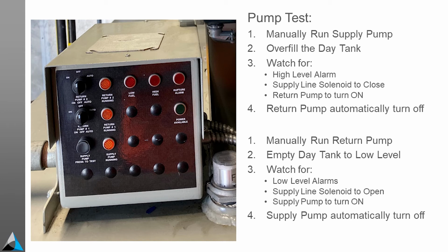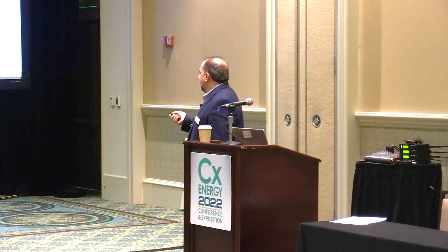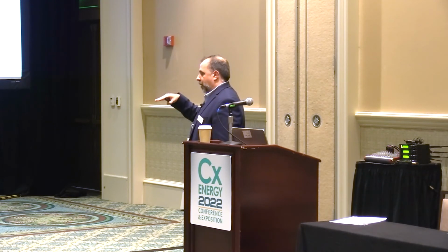So I'm ready to test the fuel system. This is generally how I'm doing it when we get to functional testing of the fuel system. I'm going to test the supply pumps. I'm going to try to overfill the day tank. This is where the videos would have been nice. In this case, I push the run supply pump button, and watch it move fuel and fill the day tank until it gets to its high level. Hopefully the sequence of operations has said at what level that is, 90%, whatever the engineer has set it at, for the float switch to kick on, shut off the supply pumps and kick on the return pumps. Make sure all that works, and then I'll reverse it. We'll run the return pump until the day tank gets to its low fuel level, and watch the opposite happen. Watch the return pumps kick off and the supply pumps kick on, and make sure that all that's happening automatically. Pretty simple, right? How hard could that be?